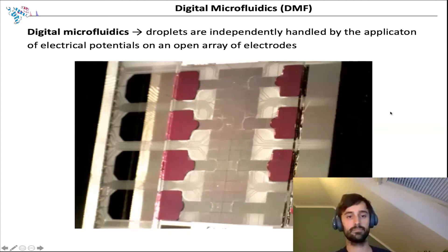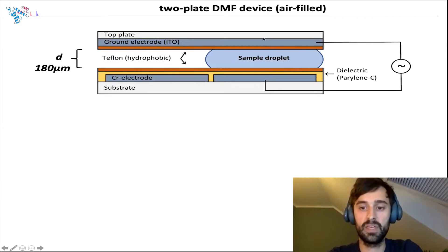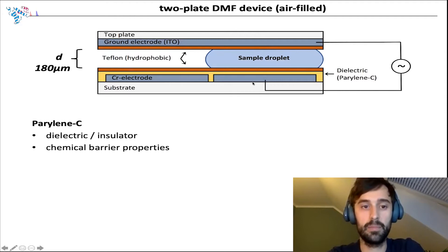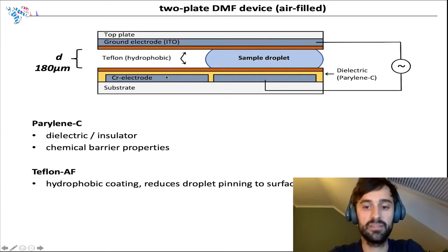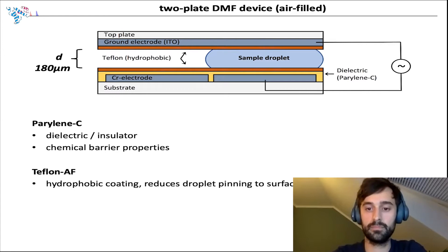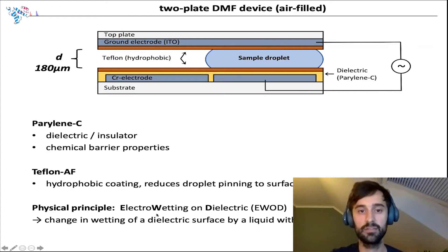The DMF chip is a so-called two-plate DMF device. The two plates are arranged in a way that forms a gap in between, where the sample is essentially sandwiched and incubated. The chip consists of a bottom substrate made of glass and electrodes. On these electrodes, a dielectric coating is applied. The top plate is made of an ITO glass slide. Both plates are coated with hydrophobic Teflon AF, which prevents any droplets sticking. To move the droplet sandwiched between the two plates from one electrode to another, the electrodes are actuated by an AC potential, with the top plate always put to ground.